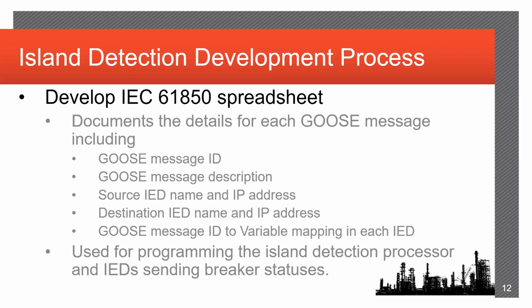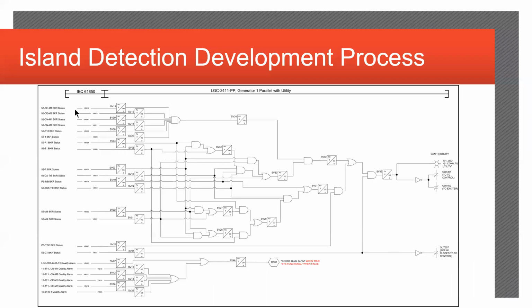Concurrent to the logic diagrams or the logic development, we were also developing an IEC 61850 spreadsheet. This is basically a document that describes in detail everything that goes into the Goose messaging, such as Goose message ID, and of course a description, source IED name and address, destination name and address, Goose messaging ID to variable mapping in each IED. You can see over here on the left-hand side, this is the IEC 61850 part of it, and then those Goose message variables get mapped into, in this case, a SELogic variable inside of the relay.